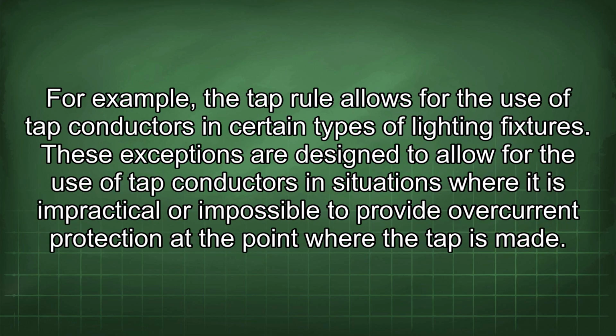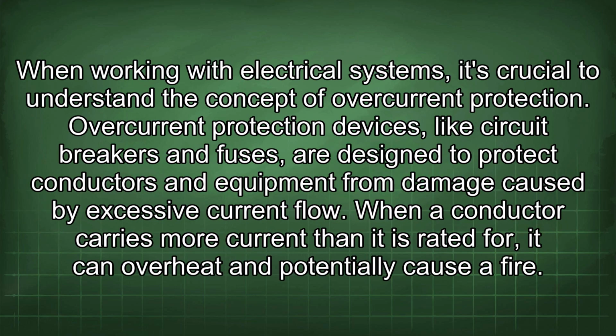For example, the tap rule allows for the use of tap conductors in certain types of lighting fixtures. These exceptions are designed to allow for the use of tap conductors in situations where it is impractical or impossible to provide overcurrent protection at the point where the tap is made. When working with electrical systems, it's crucial to understand the concept of overcurrent protection. Overcurrent protection devices, like circuit breakers and fuses, are designed to protect conductors and equipment from damage caused by excessive current flow.